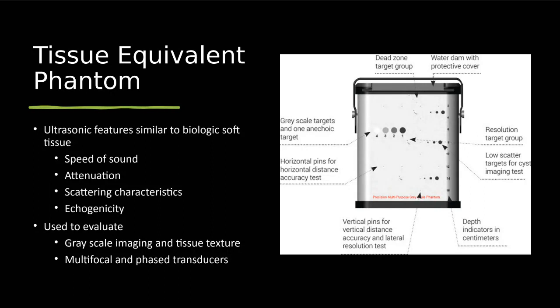They place these little foci in there, if you can see on that image. See those gray circles right in the middle? We use that to help with the axial and lateral resolution that they're testing for. Again, that echogenicity, that output power. So they're putting these variable little things in this phantom to help us test for multiple different components. So we're using this, or they're using it, for a lot of different reasons.